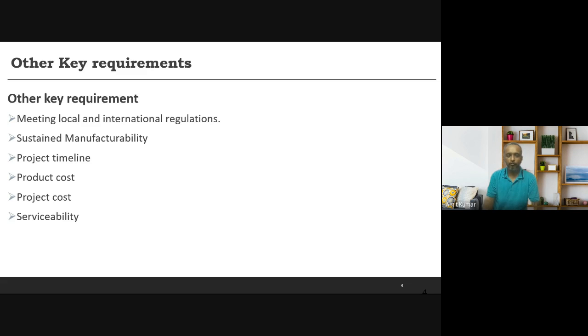So what we look for is serviceability. We design in such a way that a component can be replaced in much less time, and the components are easily available to the customer. And reliability itself is another key requirement, which we try to cover under serviceability, so that preventive maintenance is not done so often. Typically, we target preventive maintenance around once a year, or, if the device is very complex or has a high level of consumables, probably once in 6 months. That is the kind of target we set when we look at serviceability.